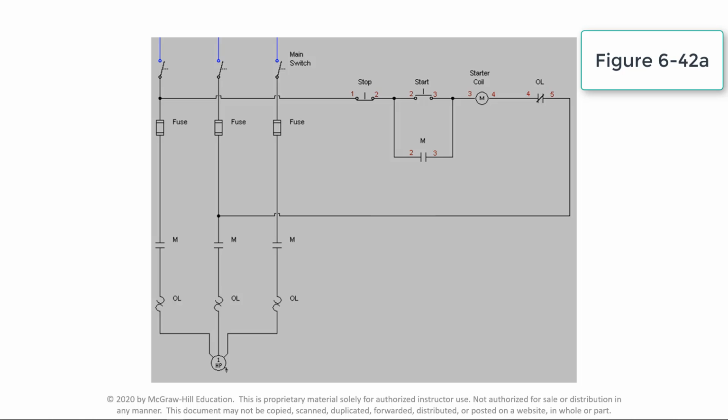Each thermal overload relay consists of the main overload block, which houses the contacts, a tripping mechanism with reset button, and interchangeable heaters sized for the motor. When the current exceeds the rated value for a long enough time, the overload contact is tripped open.